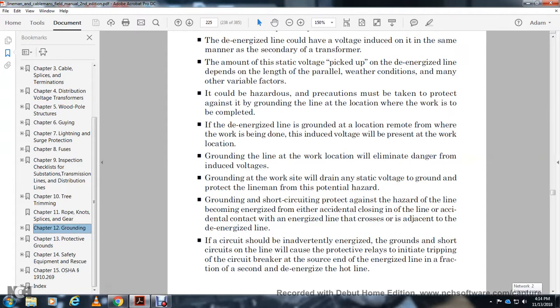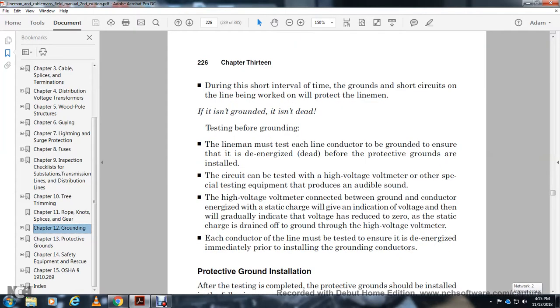If the circuit should be inadvertently energized, the ground and short circuit on the line will cause the protective relay to initiate tripping of the circuit breaker at the source end of the energized line in a fraction of a second, de-energizing the hot line. During that short interval, the grounds and short circuit on the line being worked on will protect the linemen. If it isn't grounded, it isn't dead.